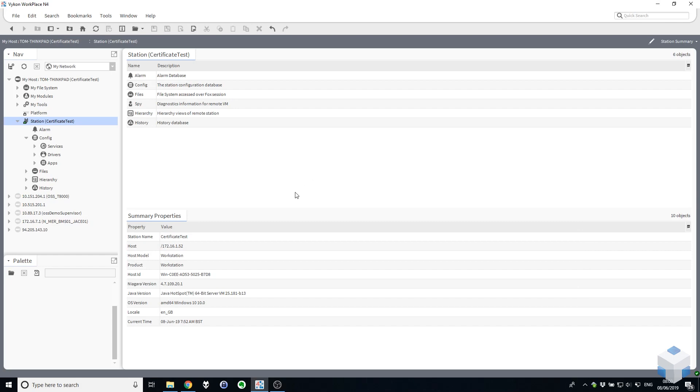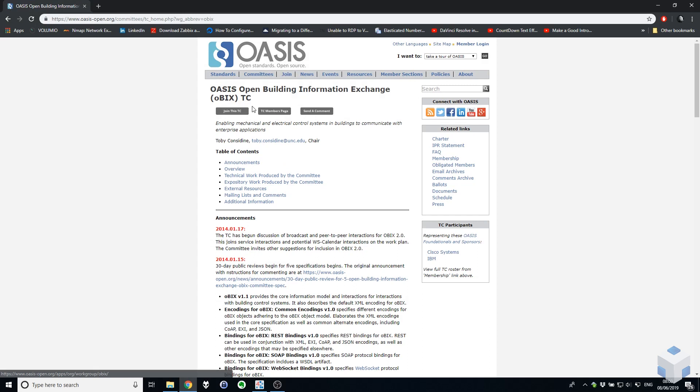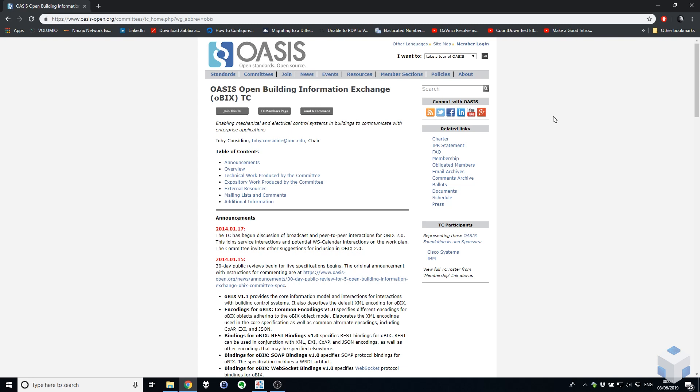So before we start let's just have a quick look at OBIX the protocol itself. OBIX is OASIS Managed Open Standard. Open Building Information Exchange is what it stands for and the best way to think about OBIX is like an early version of a modern RESTful JSON based API. It still uses HTTP as its transport mechanism however it's XML based, a bit heavier and just a bit older.